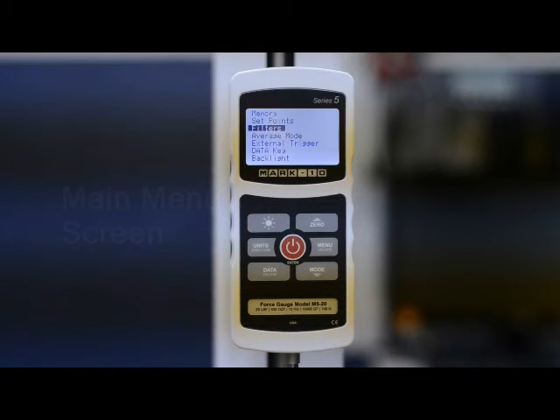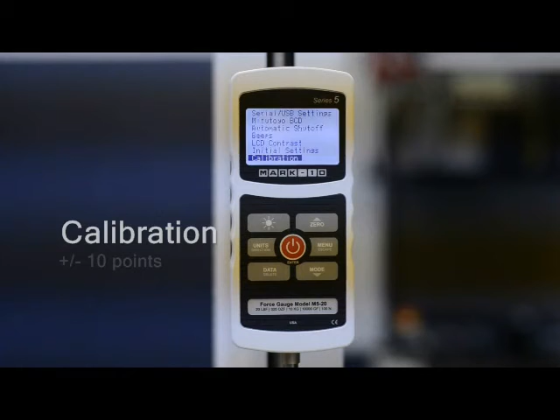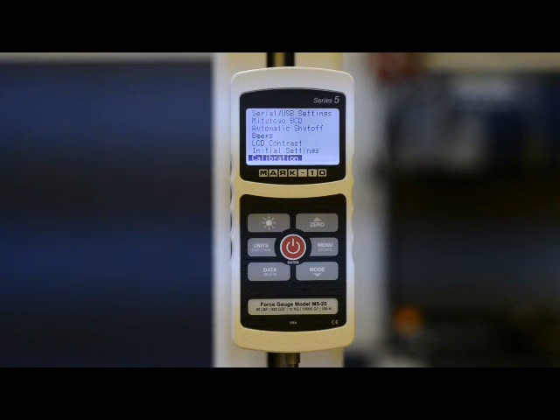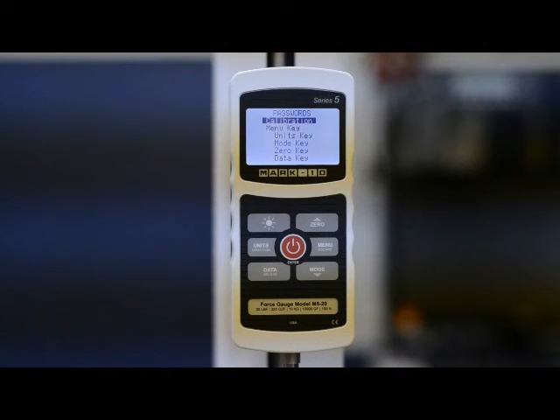You can set up a filter, which is useful in high vibration environments, to smooth out the readings. There's also a calibration area where there are user prompts that allow you to calibrate the gauge at up to 10 points in either measurement direction. You can also set up a password to prevent access to certain areas of the gauge, including the menu, certain key presses, and the calibration. This is good for production environments.